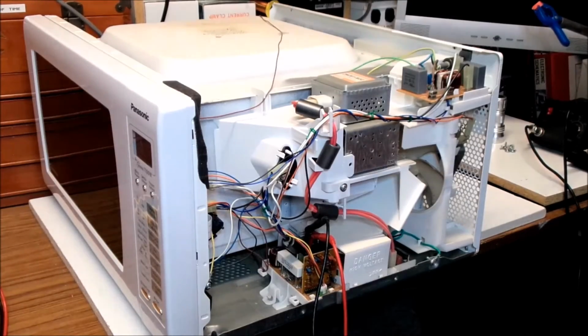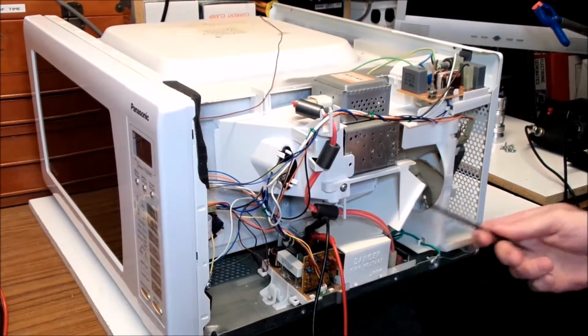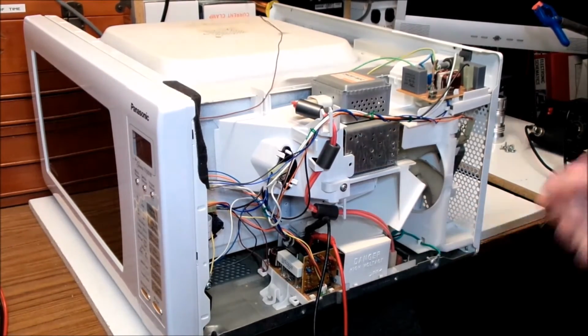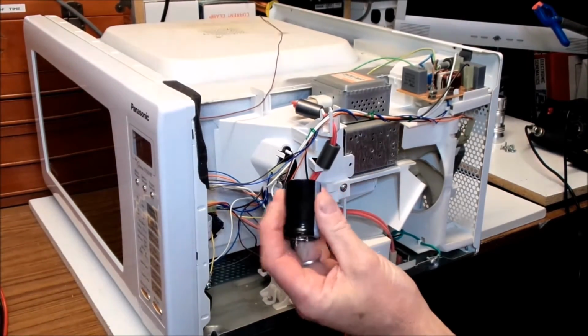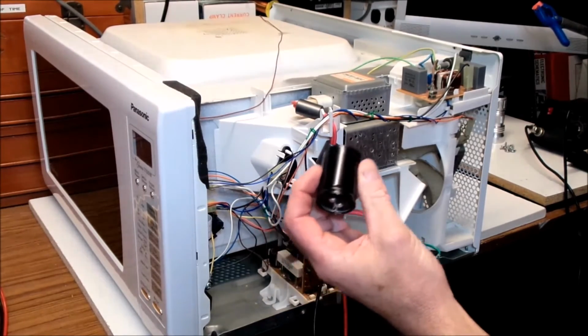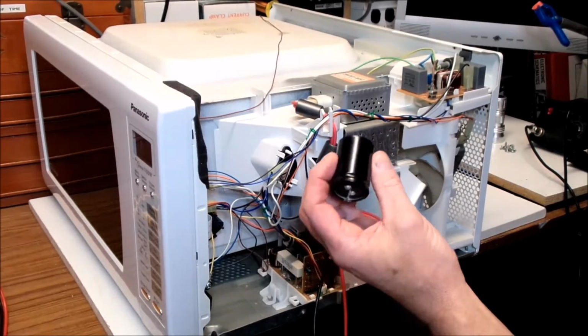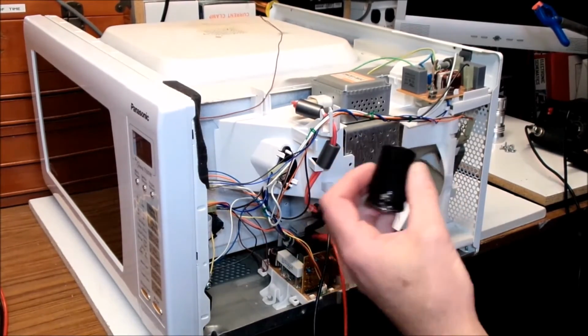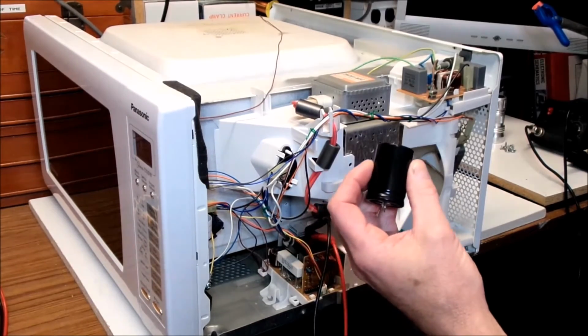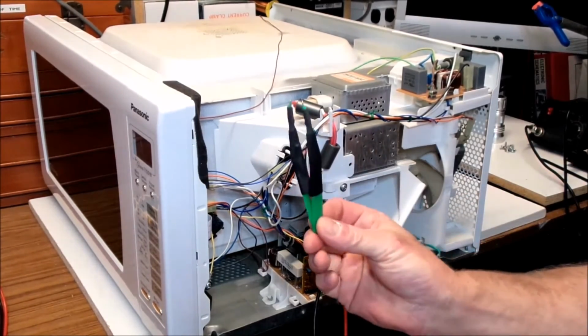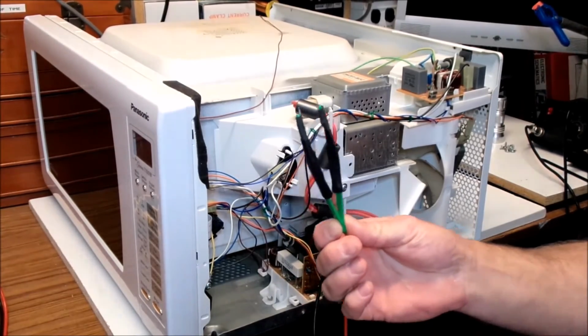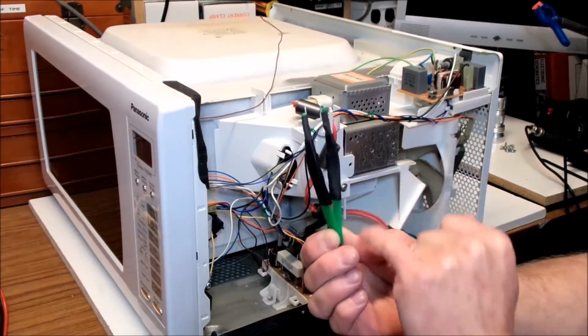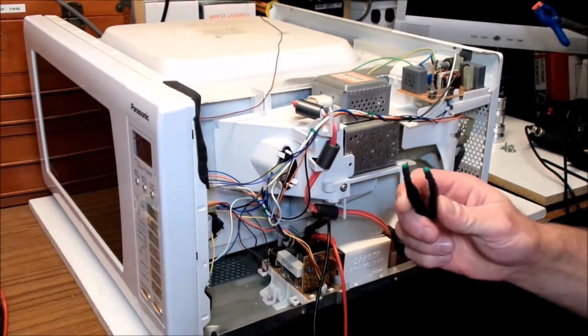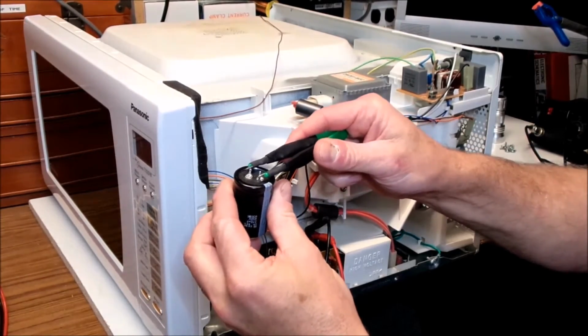Another safety caution: when working on high voltage areas like the transformer or power supply area, you'll generally find a large capacitor, similar to this one - an electrolytic capacitor. This holds charge and you can get quite a shock if you don't discharge it after turning the power off. So I've made a plastic pair of tweezers with a couple of resistors joined in series, which I put across the terminals on the capacitor to drain them off.